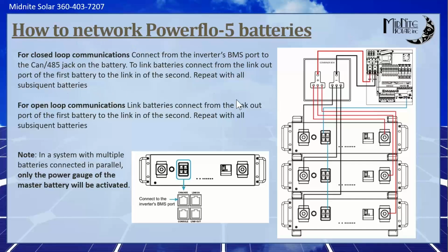On an actively balanced battery, cable lengths are less critical than on a passively balanced battery. In this installation, I'd try to make all my negatives one length and all my positives one length. They don't have to match each other, but they should all be consistent. What you're trying to do is keep the resistance of the whole circuit the same. The PowerFlo 16 is more forgiving because the batteries will actually tell each other to take the current and balance out over time when you're charging.